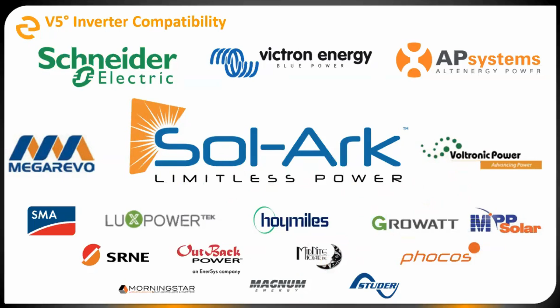With Sol-Ark, along with a couple of other manufacturers, we have full UL safety certifications. Specifically with the V5 and basically any model Sol-Ark, the 5K, 8K, 12K, 15K, we have UL 9540, and the batteries have also undergone UL 9540A testing. That 9540A test includes cell level, module level, and unit level tests to investigate thermal runaway. We have done that with the V5 batteries with all of those different Sol-Ark models.